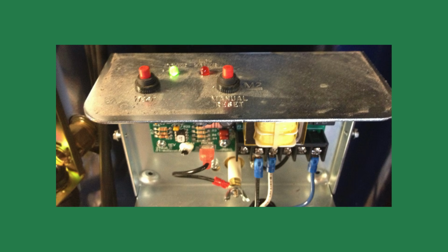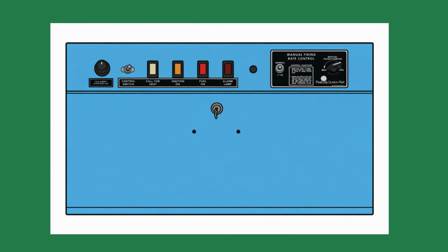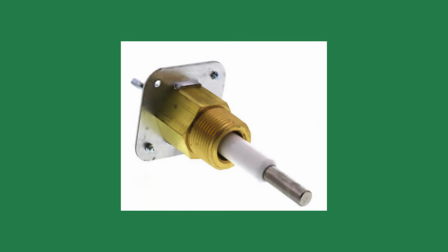Testing is simple. Most controls have a test button that simulates low water, where you can safely drain the boiler below the elevation of the probe. This can be more challenging on a hydronic system because all the piping is filled with water above the boiler. Always perform the test while the burner is running and verify the burner shuts off. I like to remove and inspect the probes every year. Be sure to drain the water below the probe first to avoid splashing yourself or the electrical components. Always follow the specific manufacturer's instructions for your model. Some probes can be cleaned with steel wool or a scouring pad, while others just need a soft rag and water.